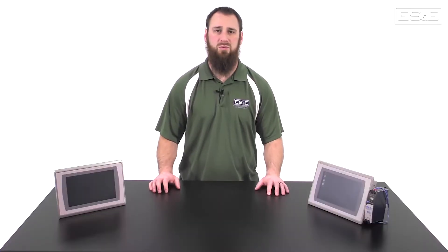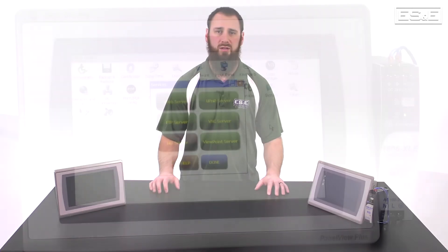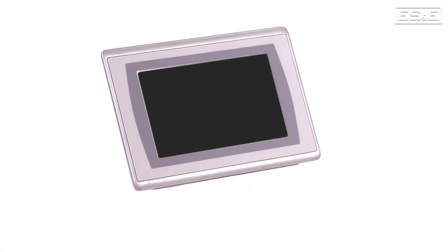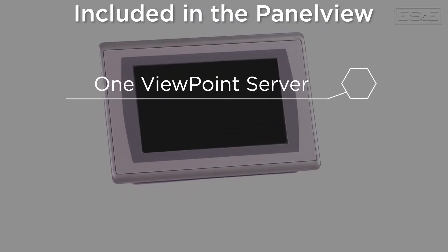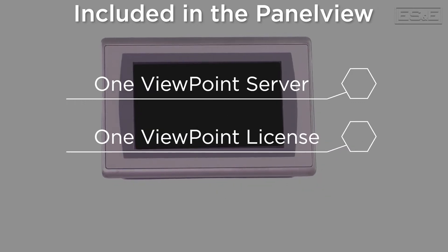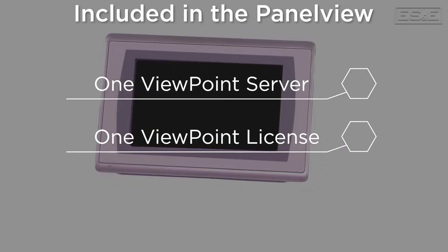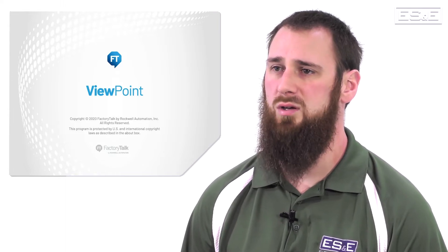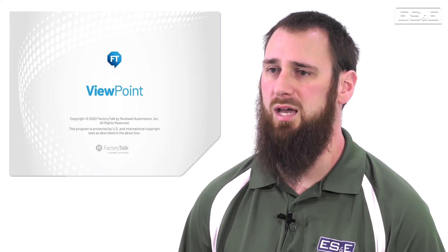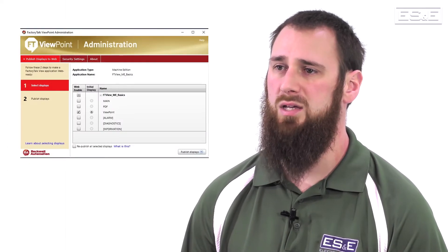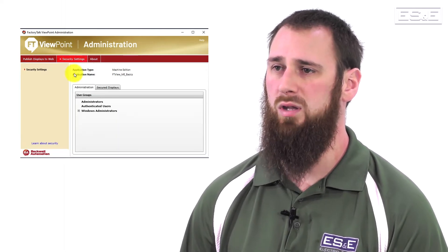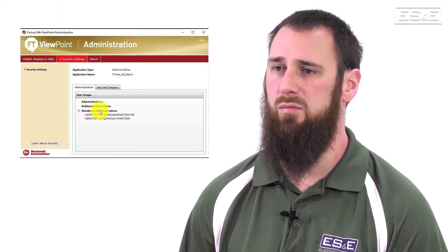The PanelView Plus 7 comes with several embedded servers, and in my opinion, one of the most underutilized servers is the Viewpoint server. When you purchase a PanelView Plus, it comes with one FactoryTalk Viewpoint server and a Viewpoint client license embedded in the PanelView. Viewpoint provides the ability to use a web browser to remotely access or view screens published by the ME application. The application allows you to replicate the same screens created for the PanelView, or allows you to create new content for remote viewing.